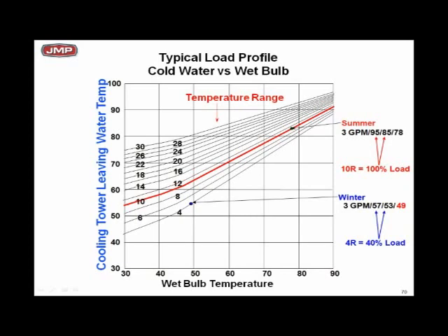It is latent cooling. It's not sensible, it's latent. So I've got to evaporate that water. I've got to work with that wet bulb in the air to do this. I've got to take this moisture and evaporate it into the air. And I just said to you, real simple, hang on to this, it's very important for the rest of your life to understand this. Cold air holds less moisture. Go get a psych chart. Let's spend some time on this. But this is a lesson you need to learn the rest of your life. Cold air holds less moisture. Just remember that statement. And as you get through your life, try to figure that out.